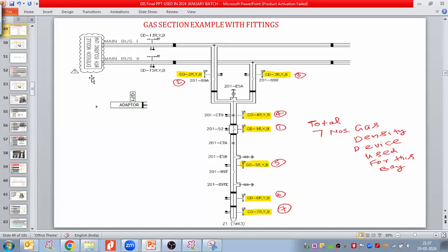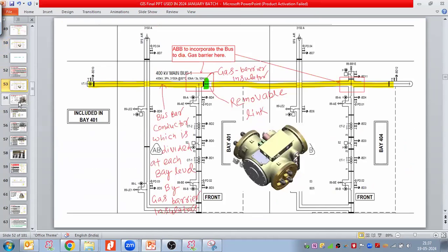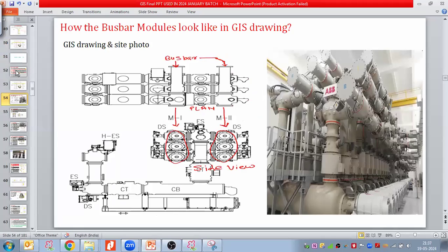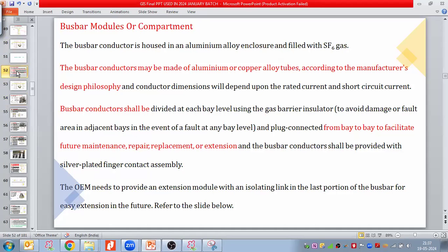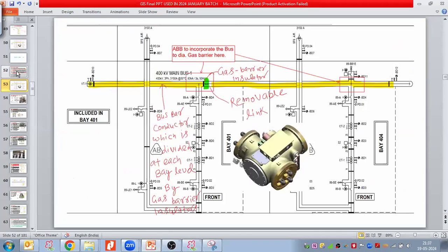See this drawing, this information came in revision one, because initially it was not given by the manufacturer. After comment, they have given this. So when you review the bus bar module, keep this point also in mind, right? So here, if you see this one, this is a plug connection or removable link. Through that, the conductor could be easily connected.